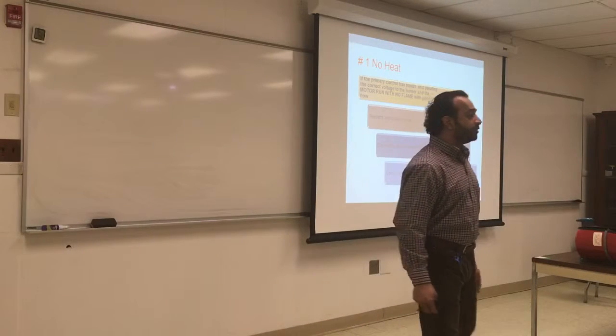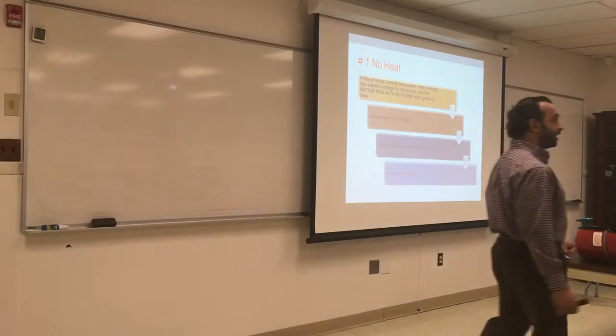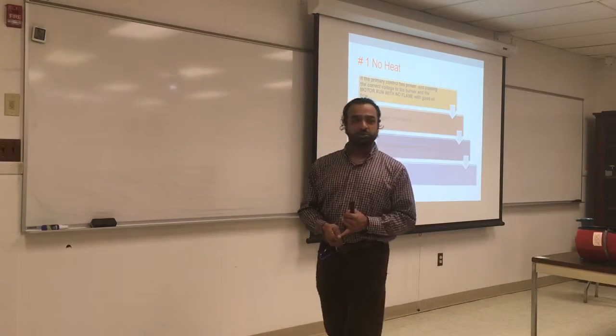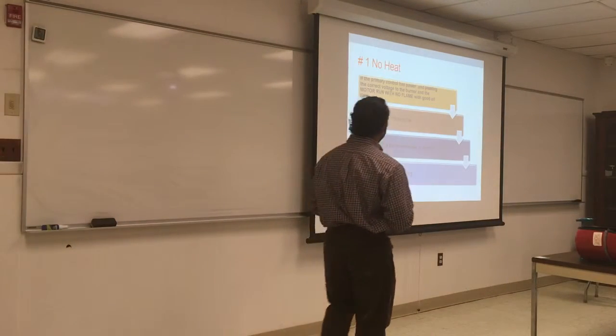Check the air setting. Again, we faced that before. If you have too much air, you will not have flame. So choke down on the air and reduce the air, play with it a little bit until it ignites. A lot of it's the air, that's true. Air is always an issue. If you have fuel, if you have ignition, the third component is the air.